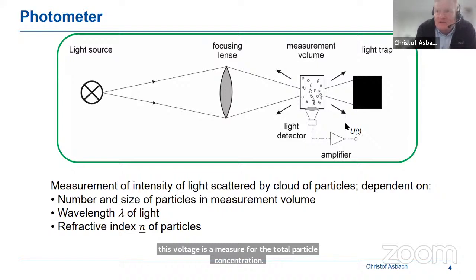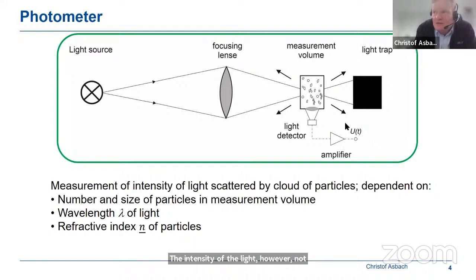The intensity of the light, however, not only depends on the particle number or volume of the particles inside the measurement volume, it also depends on the size of the particles. That means eventually the particle size distribution. It depends on the wavelength, which of course is given for a given light source, but it also depends on the refractive index of the particles. Just as a simple example, if you have a black and a white particle of the same size, the white particle will scatter more light than the black particle, and that's simply because of the refractive index.